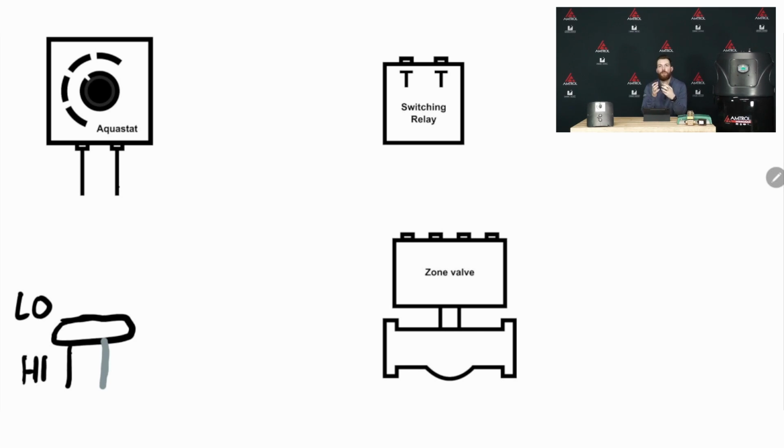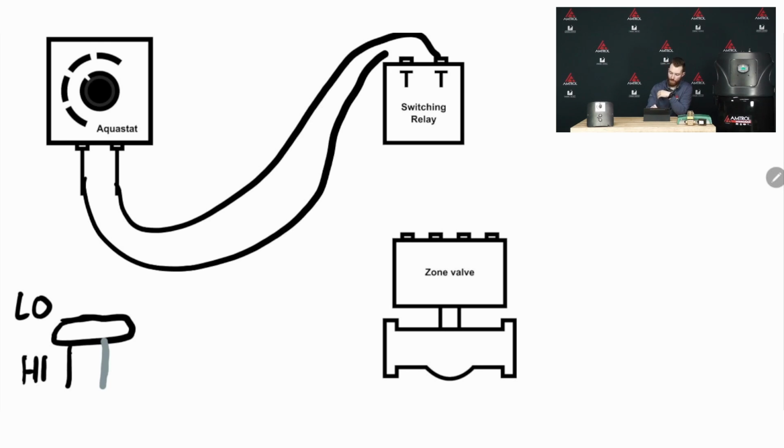The two wires on your mechanical Aquastat, those two larger gauge black wires, they're interchangeable. They're just thermostat wires. They're meant to be used as TT inputs. So with that Aquastat, we run those two wires over to our TT inputs, and we'd be good to go. Very straightforward, very simple. Every time that Aquastat calls for heat for the Boilermate, it will activate that zone on your switching relay, which turns on your circulators, fires on your boiler, your furnace, whatever you have, and will get heat over to your hot water maker.